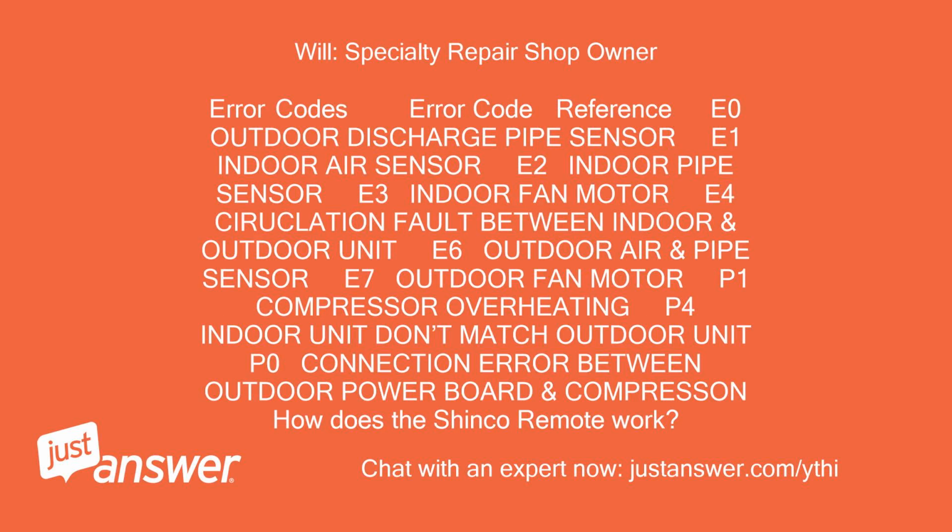Error code reference: E0 outdoor discharge pipe sensor, E1 indoor air sensor, E2 indoor pipe sensor, E3 indoor fan motor, E4 circulation fault between indoor and outdoor unit, E6 outdoor air and pipe sensor, E7 outdoor fan motor, P1 compressor overheating, P4 indoor unit doesn't match outdoor unit, P0 connection error between outdoor power board and compressor.